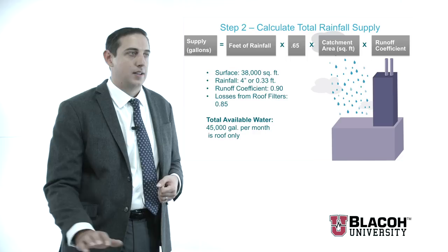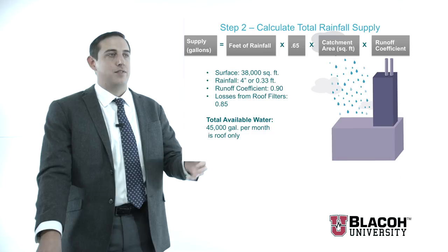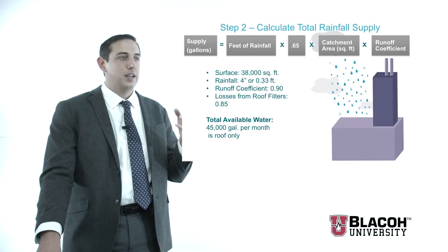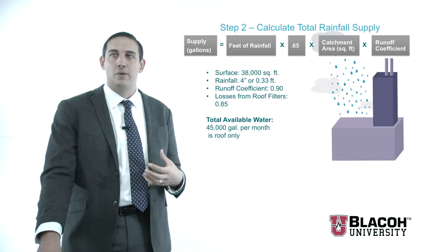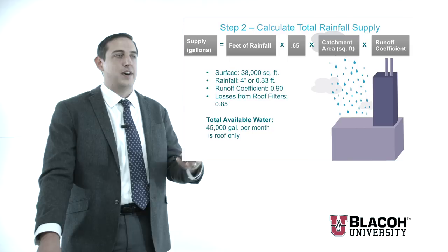Bringing back the equation discussed earlier: feet of rainfall times the loss factor times the catchment area times the runoff coefficient. I have approximately 38,000 square feet of catchment area, four inches of rainfall or approximately 0.33 feet, a runoff coefficient of 0.9 — being somewhat conservative in sizing — and a loss factor of 0.65. Calculating that through, my total available water is approximately 45,000 gallons per month, which is about an average size collection for a small commercial building like this.